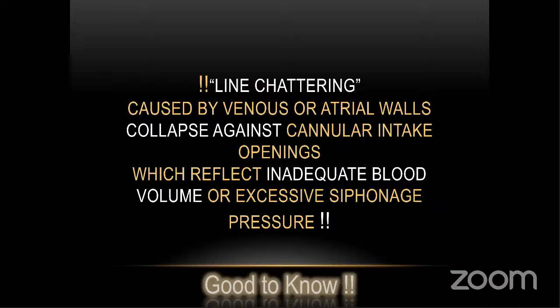Line chattering is caused by a venous or atrial wall collapsing against the cannula intake openings, which reflects inadequate blood volume or excessive siphonage pressure.